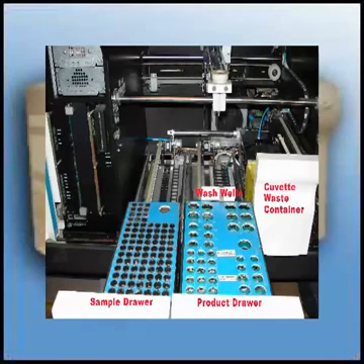Below the plexiglass cover there are two drawers. The one on the right is the product drawer and is used for reagents, quality control, and calcium chloride. The one on the left is used for samples and Owren-Koller buffer.